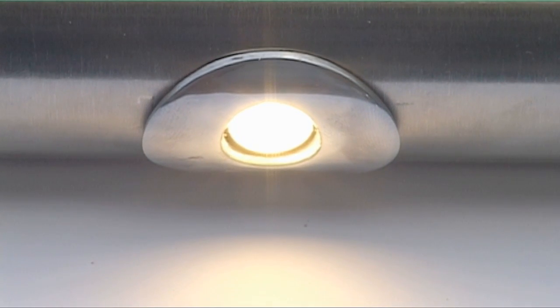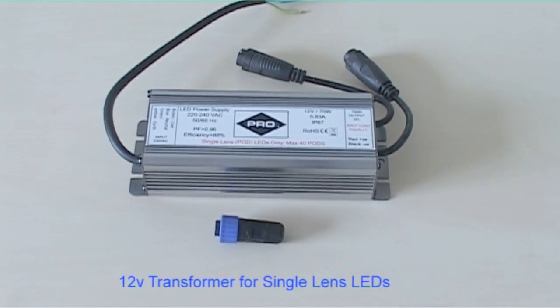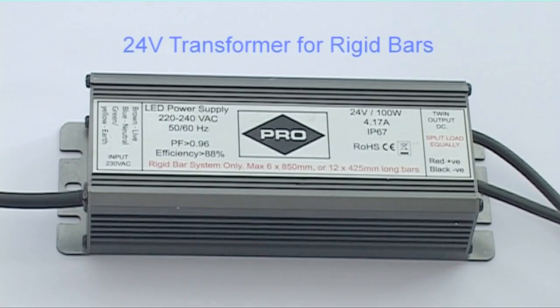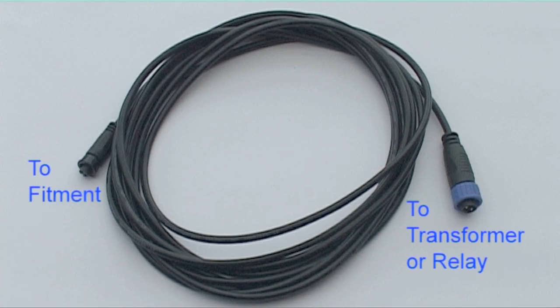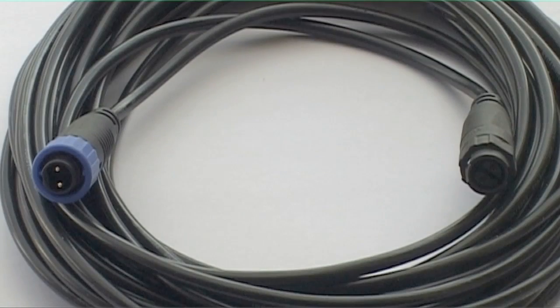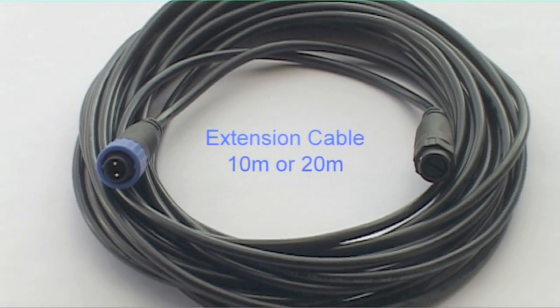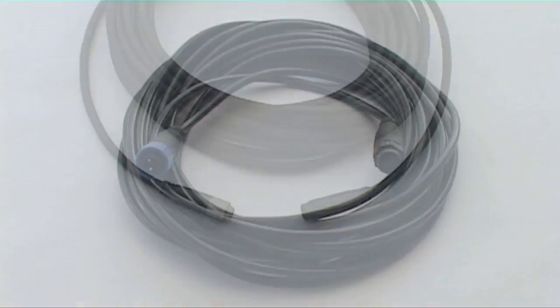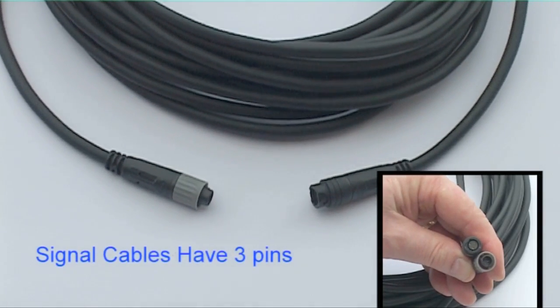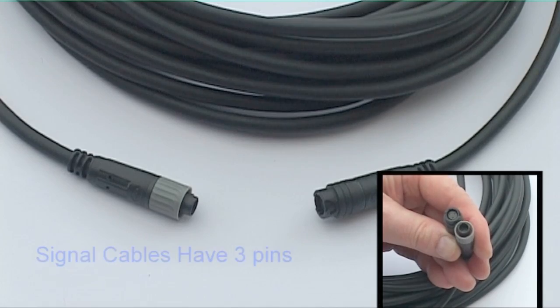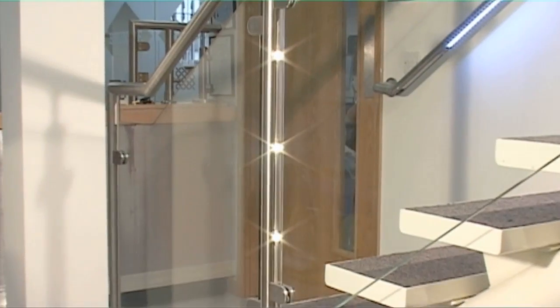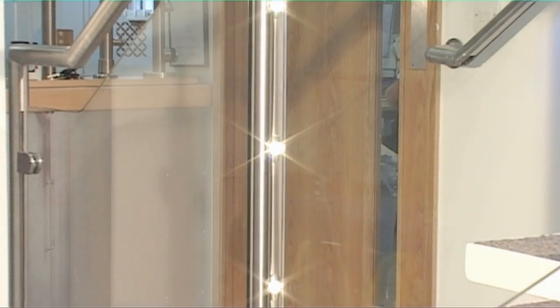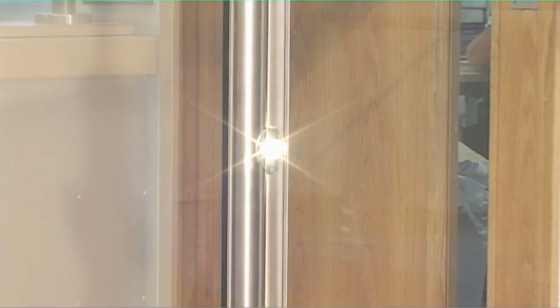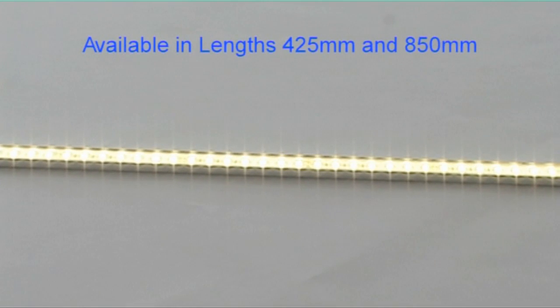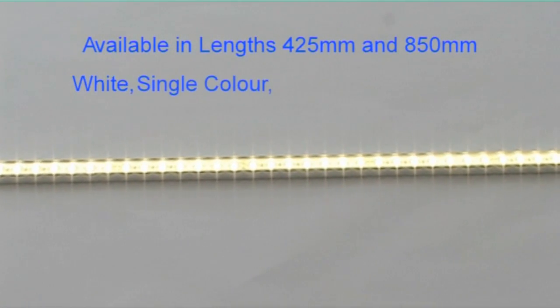The main components of the Illumirail handrail lighting system are two types of transformer, one 12 volts and the other 24 volts. Connection cables to link transformers to fitments. Extension cables, which allow transformers to be located further away from the fitments. Signal cables, which link motion detectors, touchscreens and control devices together. And then the two different types of fixture, which are single lens pod LEDs and rigid bar lights. These come in two lengths and can be white, single colour or colour changing.